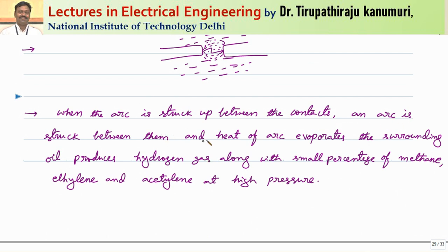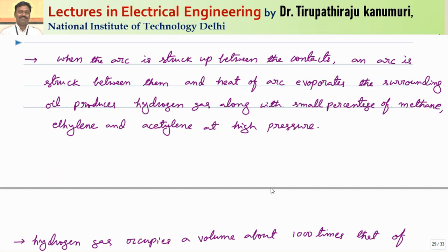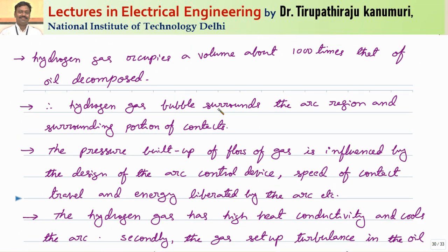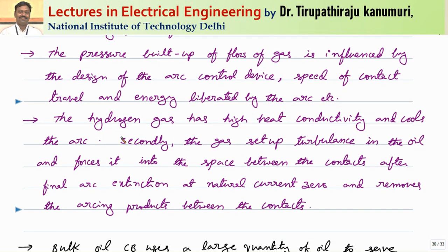When the arc is struck up between the contacts, the heat of the arc evaporates the surrounding oil, producing hydrogen gas along with a small percentage of methane, ethylene and acetylene at high pressure. This hydrogen gas occupies a volume of about 1000 times that of the oil decomposed. The hydrogen gas bubble surrounds the arc region and the contacts. The pressure buildup is influenced by the design of the arc control device, the speed of contact travel, and the energy liberated by the arc.